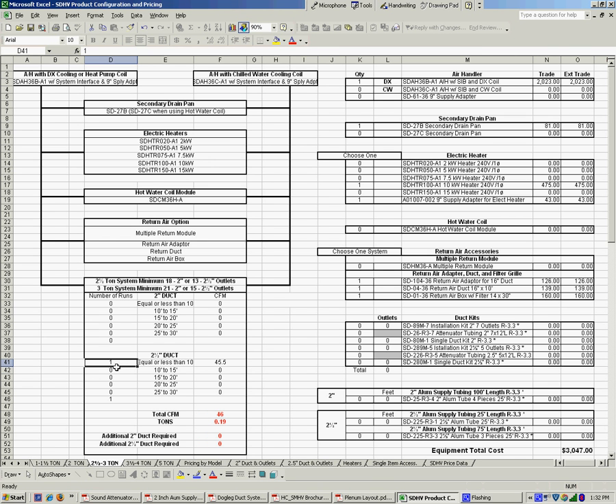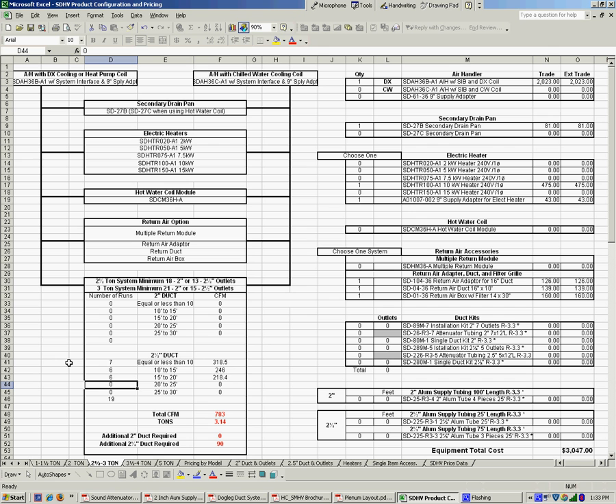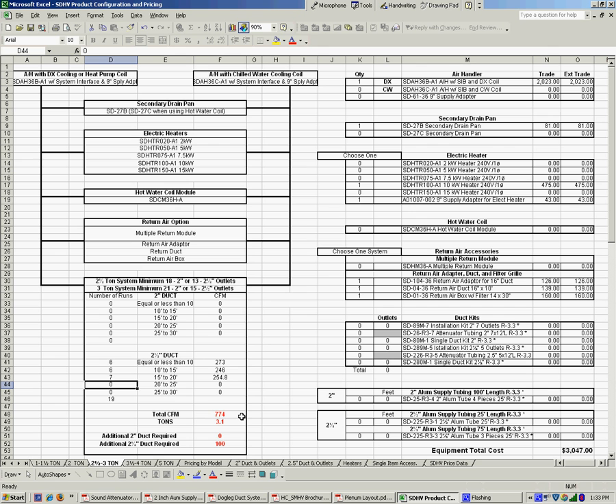So let's say we have a job that we really don't want to put that many outlets in it. I don't have the space or don't think aesthetically it's going to look good. We can come back and say let's put in 7 of the less than 10 and 6 of the 10 to 15, 6 of the 15 to 20. In this case we actually got more CFM than we want, maybe a little more than we should have. So let's change one of those. Still gives us pretty close to what it would be. Probably an ideal situation. Probably pretty close right there. We're looking for about 750, we're at 774 CFM, 3.1 tons, means we got a nice slow velocity on all the registers but plenty of CFM to satisfy the job.